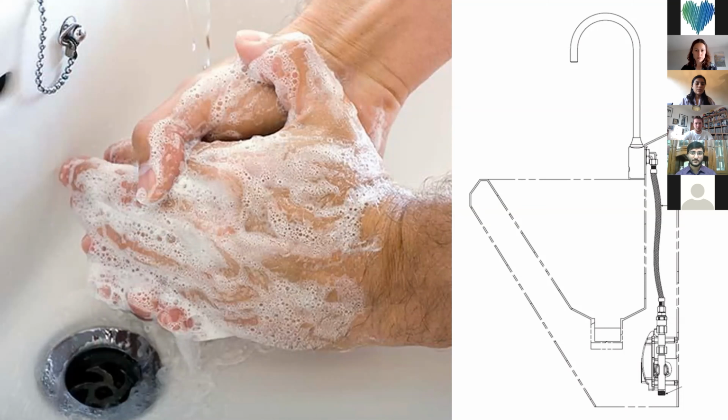And so this is a cross-sectional drawing of a sink. And instead of offsetting the faucet, in this case, when turned on, the water hit the drain directly. And within this drain area, there's often a biofilm that carries bacteria. And given the splash that occurred, this infected people around in the room. And so this obviously wasn't going to work.